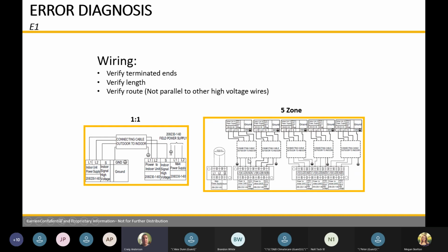5-zone units or 2-zone, 3-zone, make sure zone A is wired with zone A, B with B, C to C. If we get the wiring mixed up, then you'll get erratic behavior of the indoor unit. We could have one indoor unit running and the fan coming on, but we have Freon going through unit C because we have the wiring mixed up. So you'll have one unit freezing and then one unit sort of running.